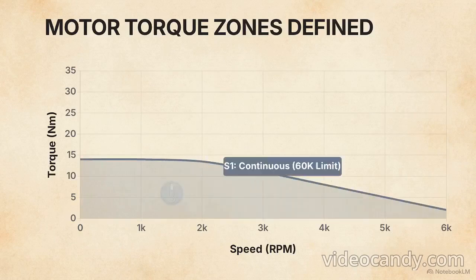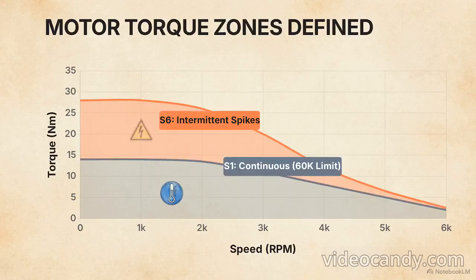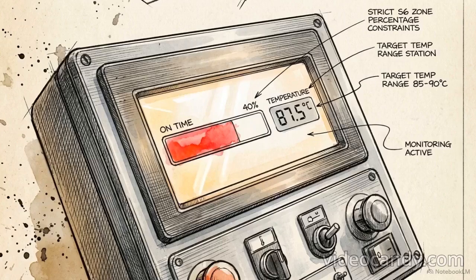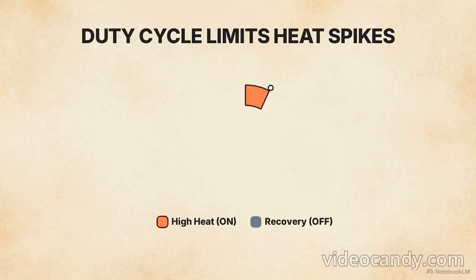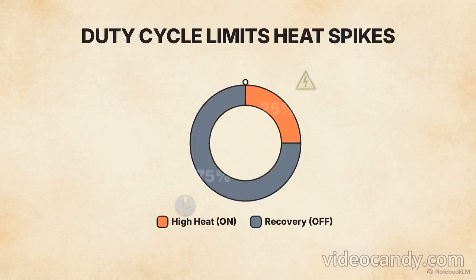This is a torque speed characteristic curve. This graph acts as the sizing matrix where mechanical, cooling, and electrical capability intersect. The lower boundary is the S1 curve. This defines the continuous operating limit, the maximum torque the motor can output indefinitely while maintaining a safe 60 Kelvin overtemperature at the housing. Above that is the S6 curve, which defines the intermittent operation zone. Operating in this space allows the motor to deliver significantly higher torque spikes than the S1 limit permits.